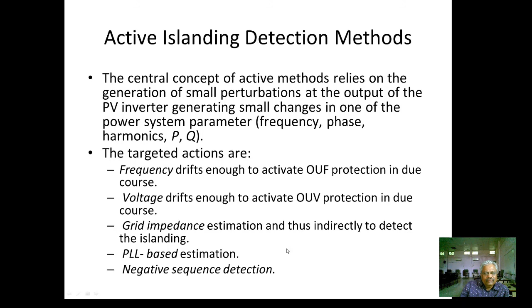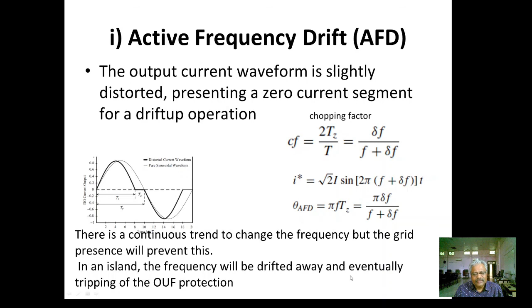Active frequency drift. The output current waveform is slightly distorted, presenting a zero current segment for a drift-up operation. This means the perturbation causes the drift up, and there is a continuous trend to change the frequency, but the grid presence will prevent this. This change in the grid frequency is opposed or controlled by the grid, but in case of grid absence, this will drift more. In an island, the frequency will be drifted away and eventually trip the over/under frequency protection. Other active frequency drift methods are slip mode frequency shift, Sandia frequency shift, active frequency drift with pulsating chopping factor, GE frequency shift, and reactive power variation.